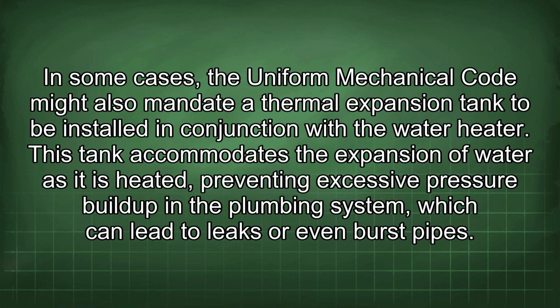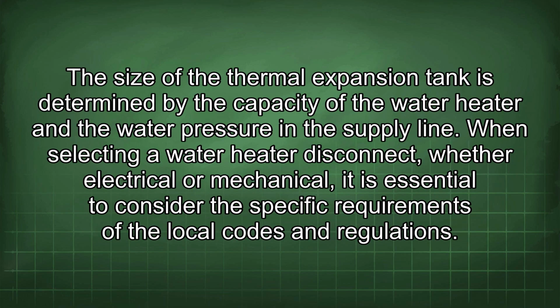In some cases, the Uniform Mechanical Code might also mandate a thermal expansion tank to be installed in conjunction with the water heater. This tank accommodates the expansion of water as it is heated, preventing excessive pressure buildup in the plumbing system, which can lead to leaks or even burst pipes.